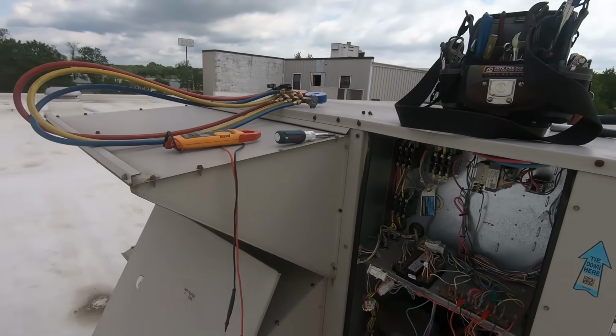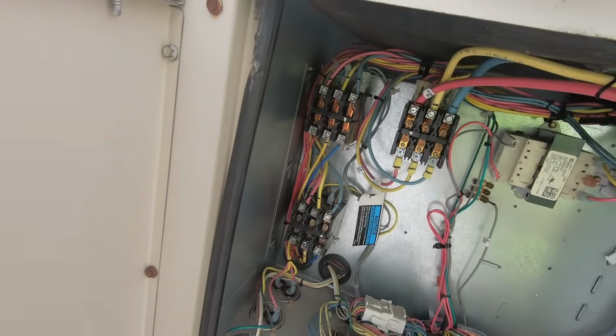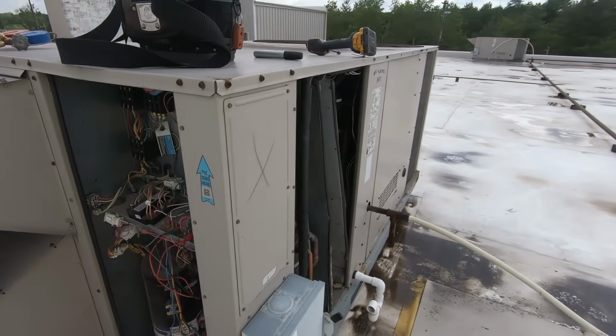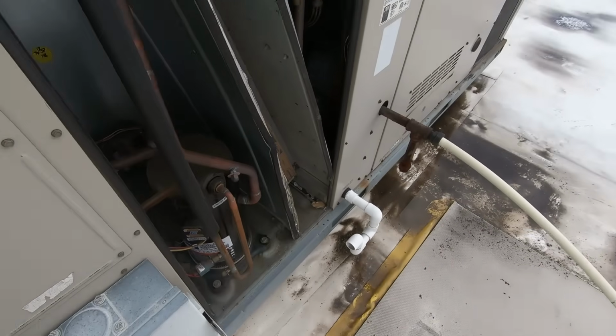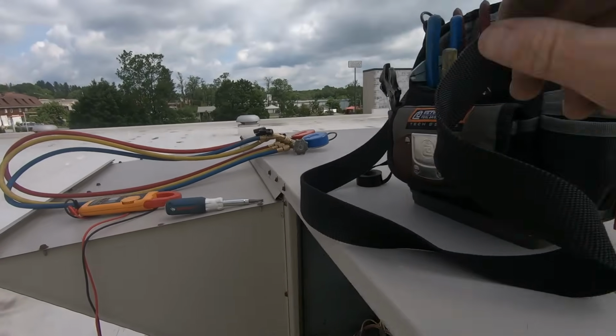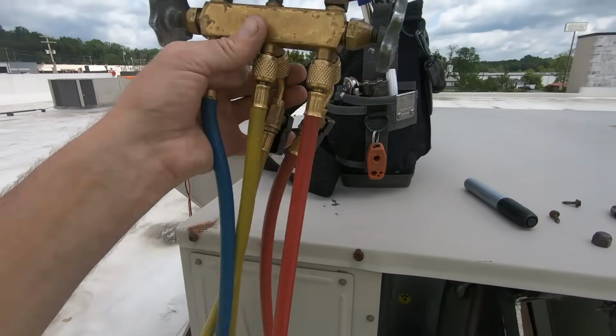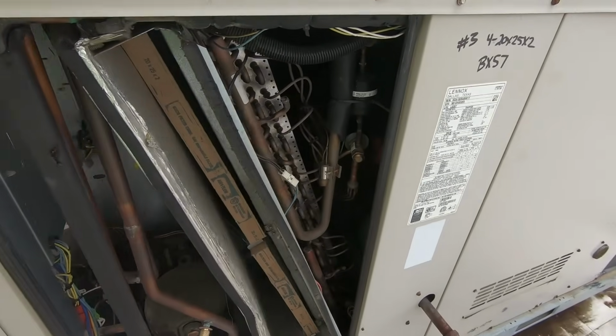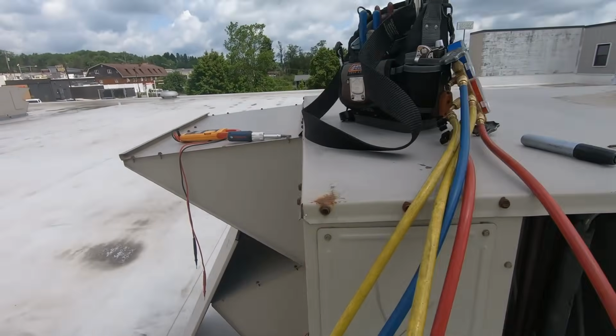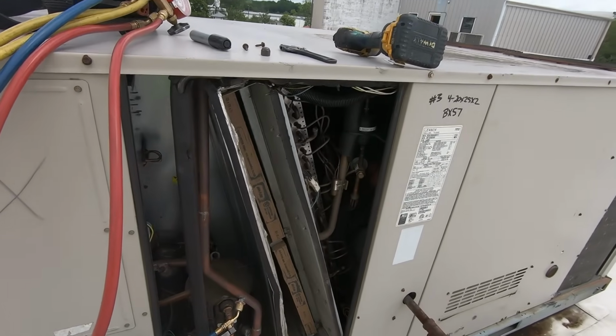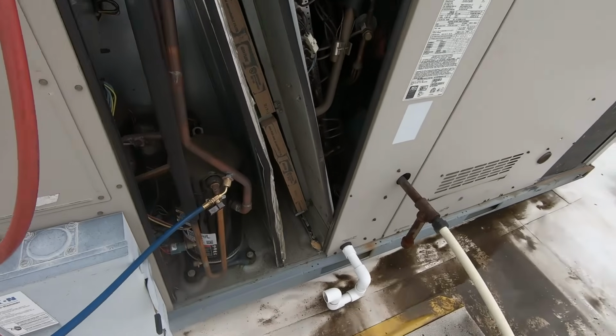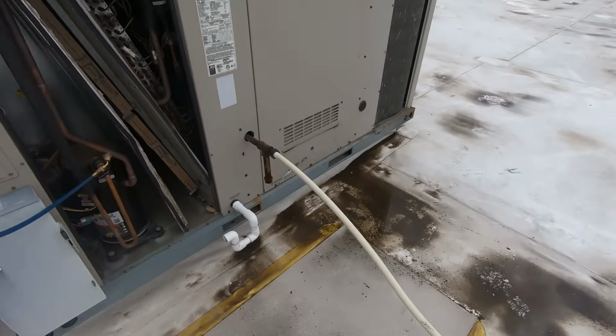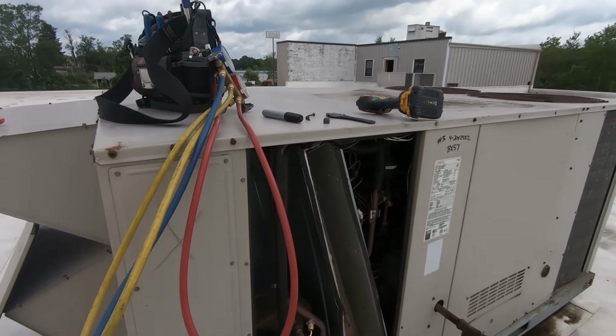Got no contactor for either compressor. Now let's see if we got refrigerant. All right, well, we have refrigerant, so we're good on that. Now let's see why this sucker's not coming on. I believe the high pressure switch may have been tripped. I did hear a click.